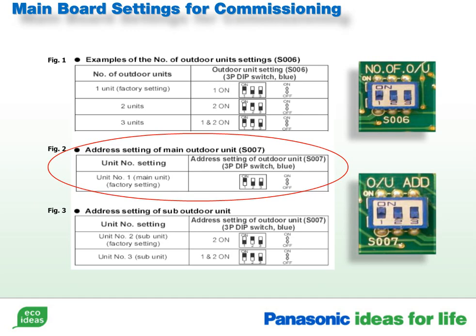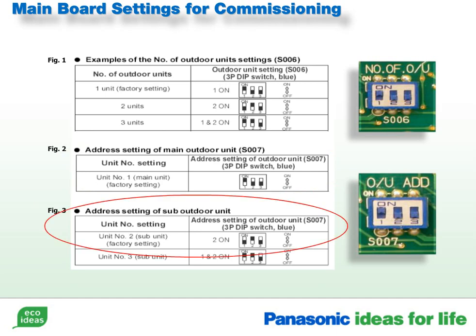In a combined configuration, the outdoor unit that is set as the main has the U1 and U2 wired to the first air handler in the daisy chain. The condenser connected to the main via the 3 and 4 terminals will need to be set as a sub-unit. This is done by configuring the outdoor unit address on the board of the sub-unit. Dip switch number 2 should be in the on position, and the others should be set to off. This condenser has now been set as the first sub-unit.